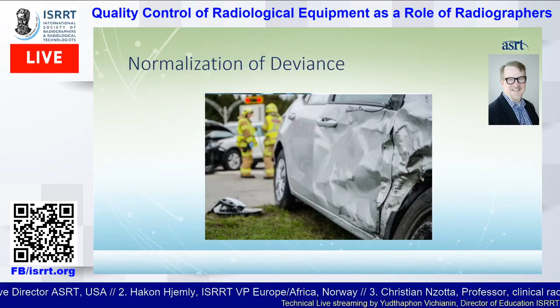Another quick example of normalization of deviance in the medical imaging world: one time when I was working as a quality control technologist, I went into an x-ray room to test the equipment, and I discovered that one of the handles on the piece of equipment was missing. And when I asked the technologist what happened to the handle, they said, well, it started getting loose over time, and it got more loose, and finally it was just barely hanging on. So we took it off and set it to the side. And I said, why didn't you call somebody to let us know, and then we could come in and fix it? And they said, well, we just kind of adapted to it over time.